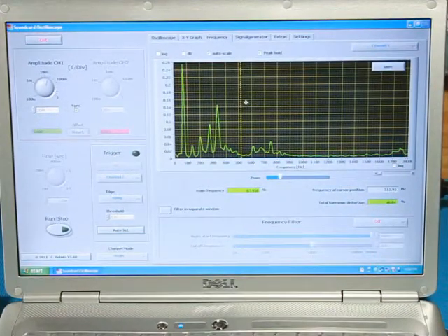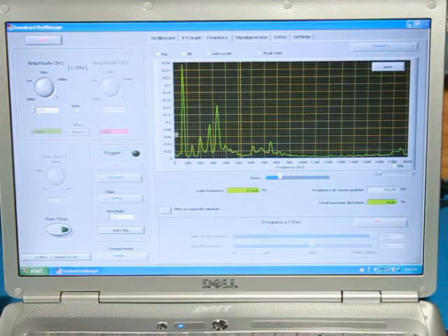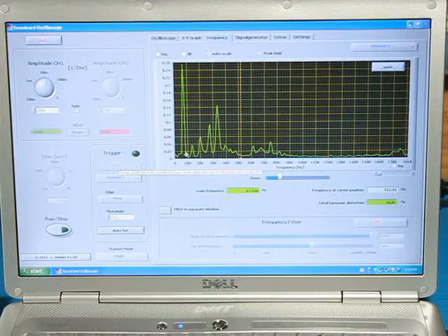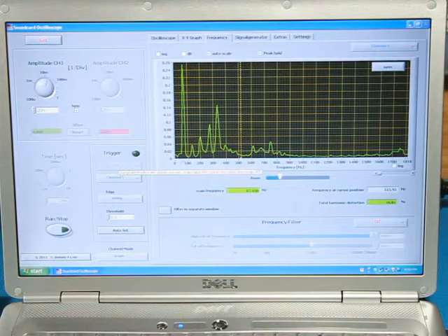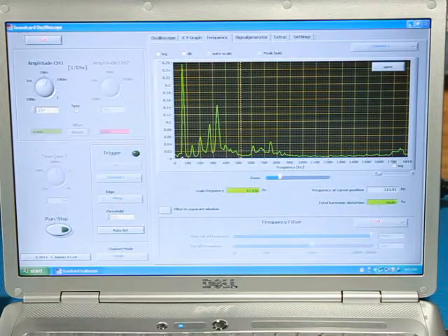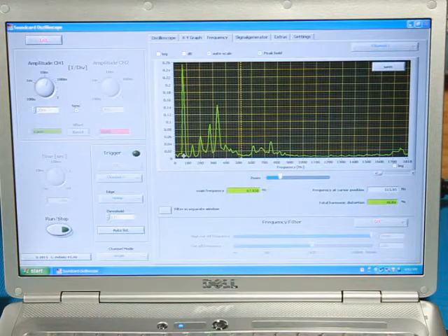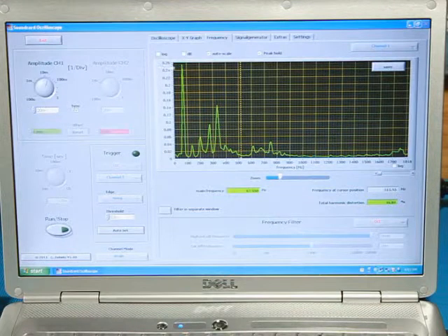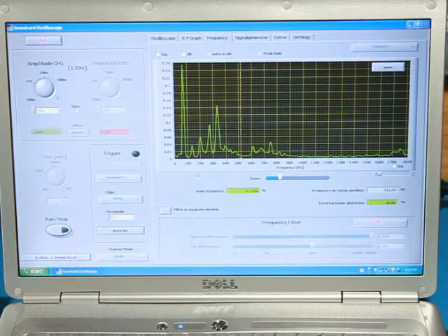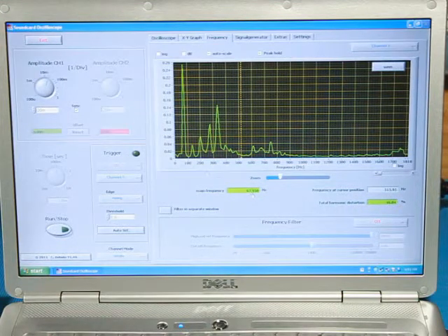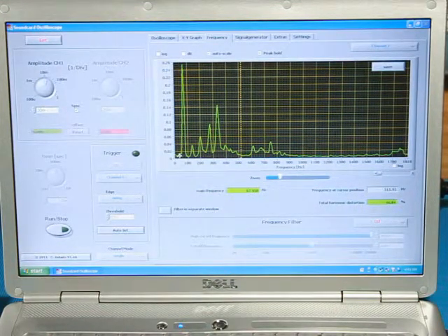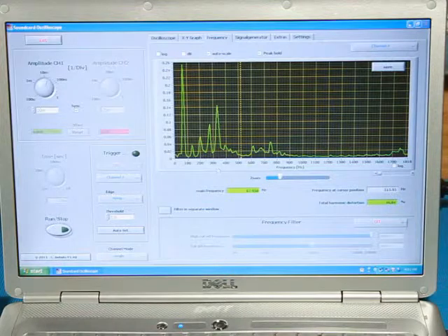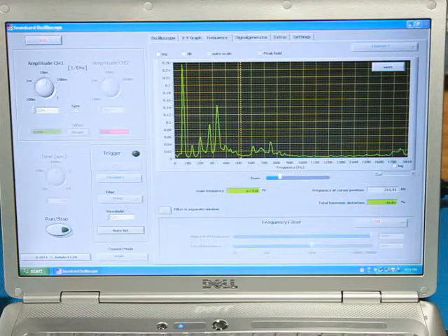I've stopped the ducted fan unit and frozen the display on the graph. As you can see, the tallest peak in the graph corresponds to the RPM of the ducted fan unit, given by the highest decibel reading or highest peak. In this case, it was around 68 hertz, which was the RPM I was running at. The next highest peak occurs roughly seven times that frequency.